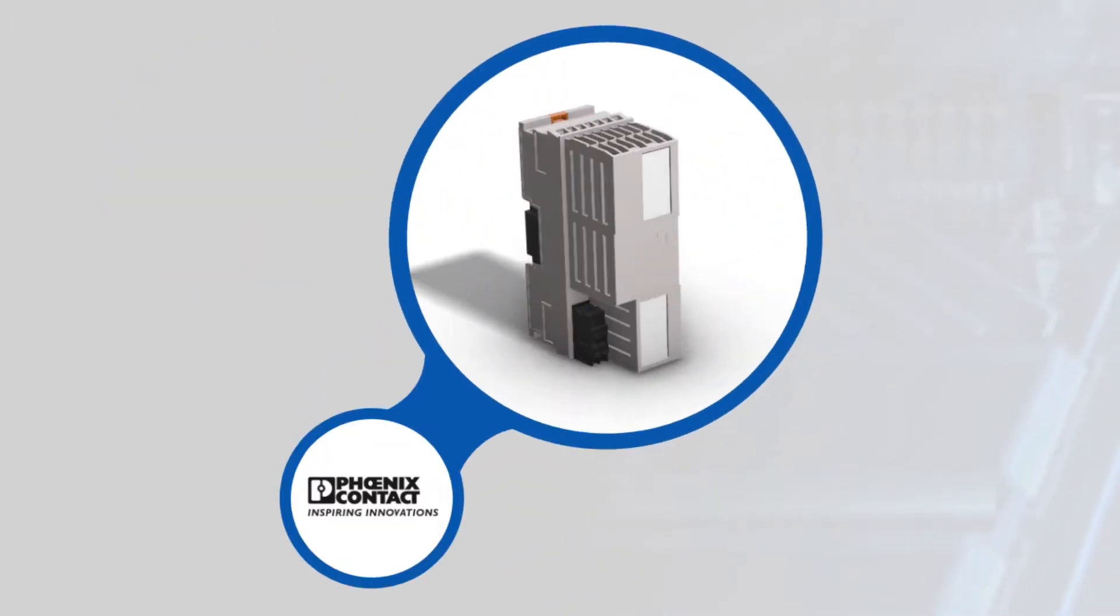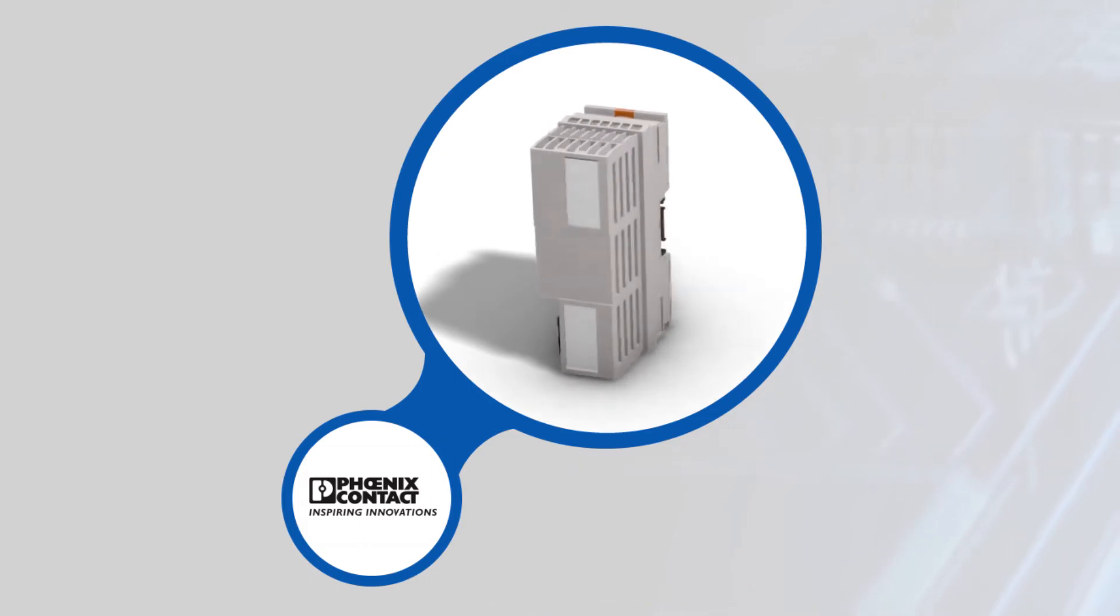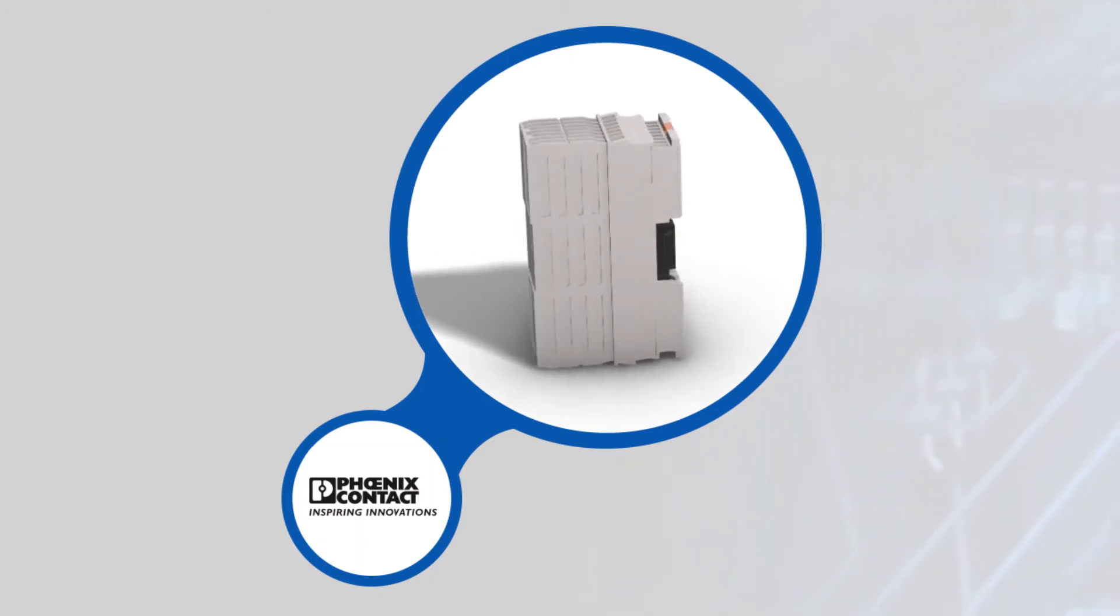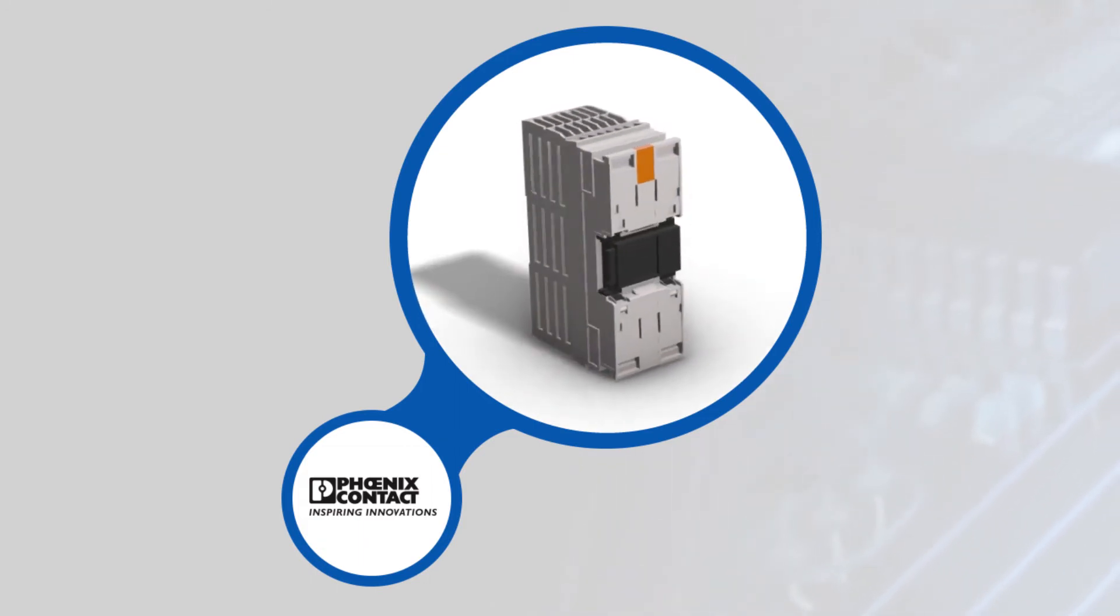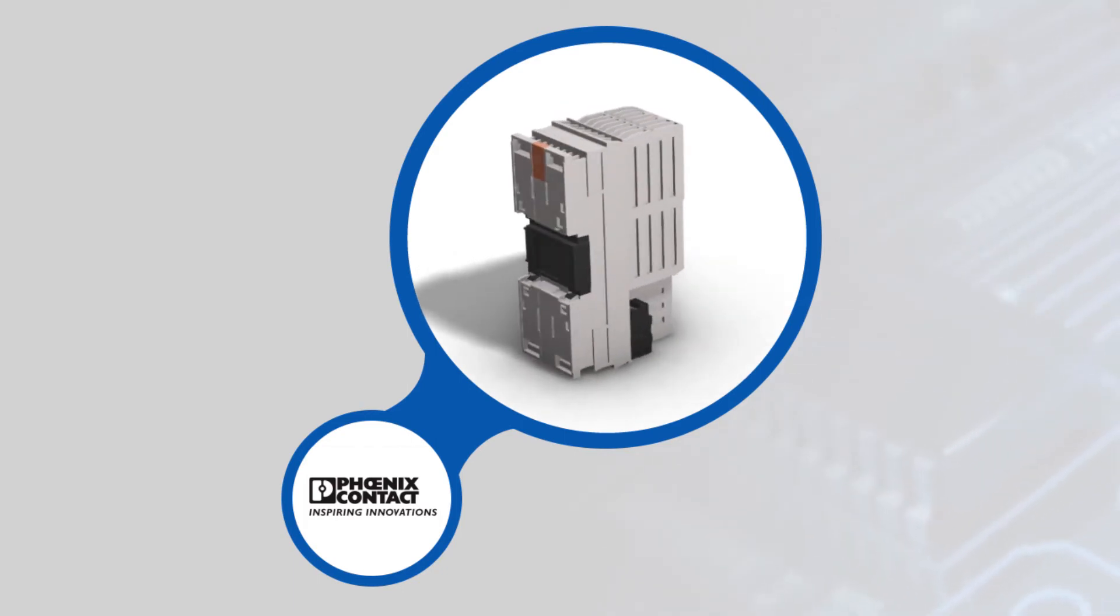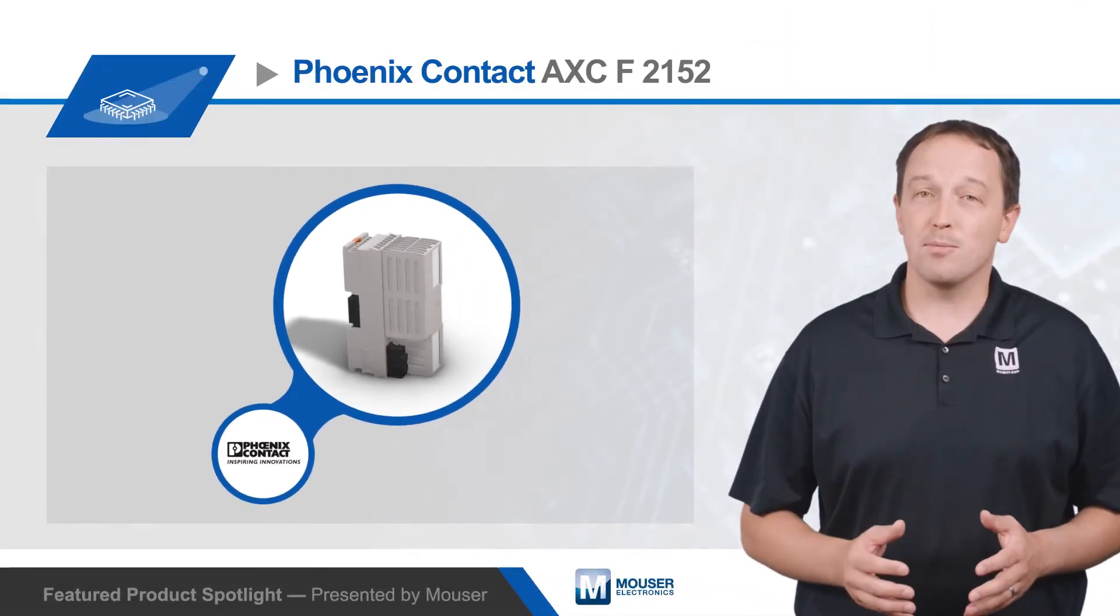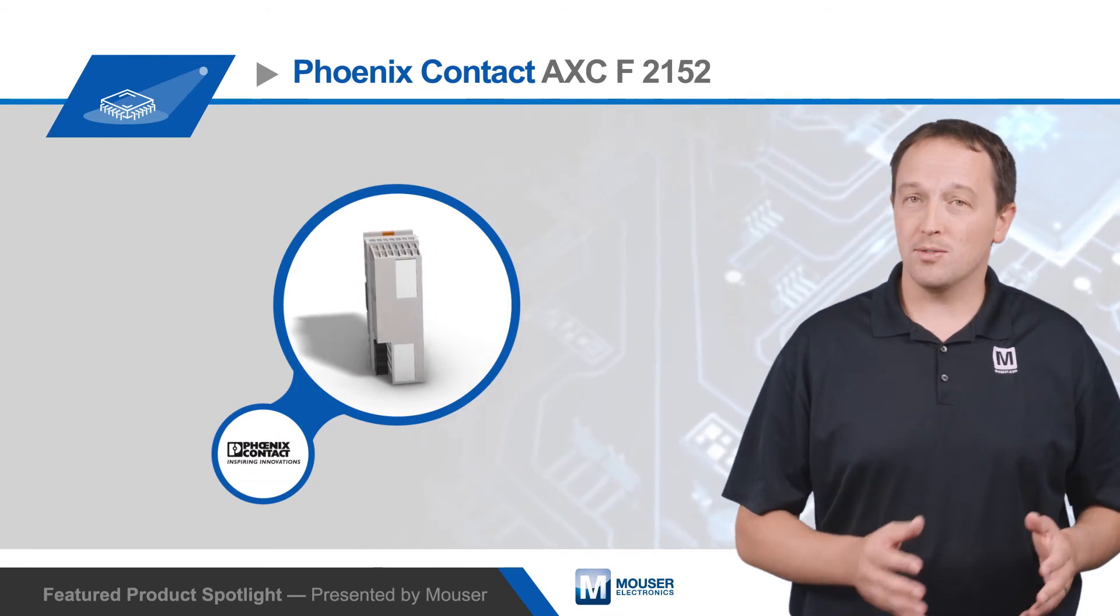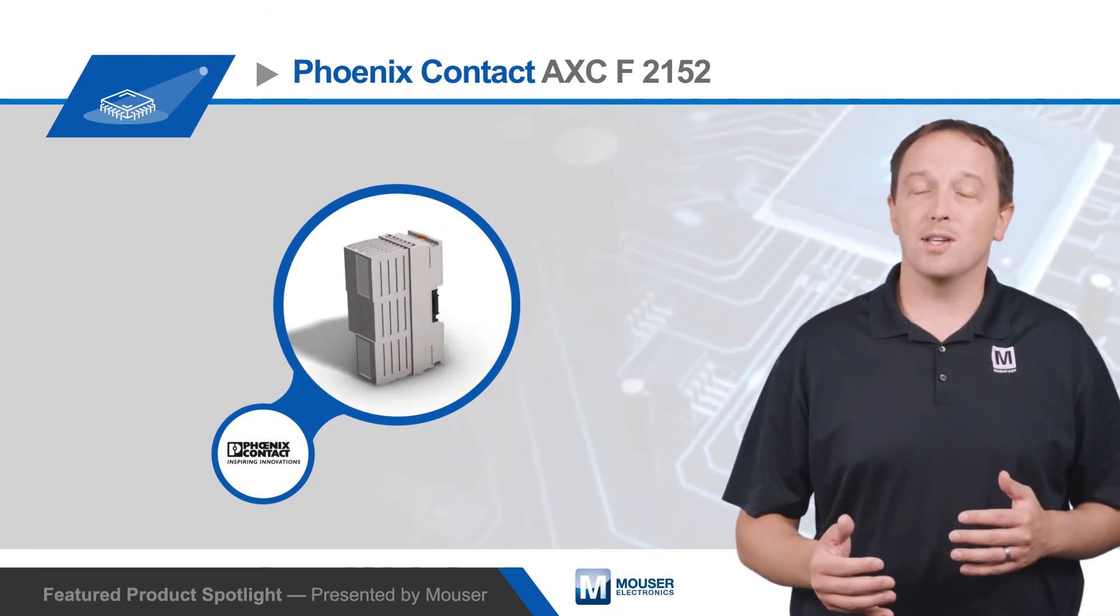The AXC F2152 controller has a hardened industrial-grade build for use in environmentally demanding applications, with the ability to withstand 30G shock, 5G vibration, and environments with 5% to 95% relative humidity and temperatures from negative 25 to positive 60 degrees Celsius.